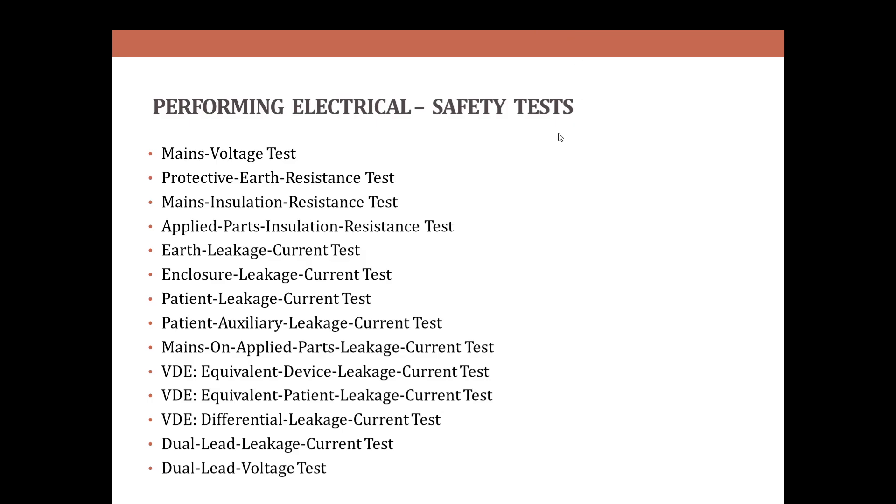Performing the electrical safety test. There are many tests like main voltage test, protective earth resistance test, main insulation resistance test, applied parts insulation resistance test, earth resistance leakage current test, dual leakage current test, dual lead voltages, and so on.